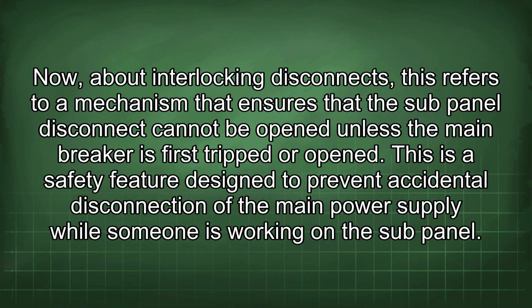Now, about interlocking disconnects, this refers to a mechanism that ensures that the sub-panel disconnect cannot be opened unless the main breaker is first tripped or opened. This is a safety feature designed to prevent accidental disconnection of the main power supply while someone is working on the sub-panel.